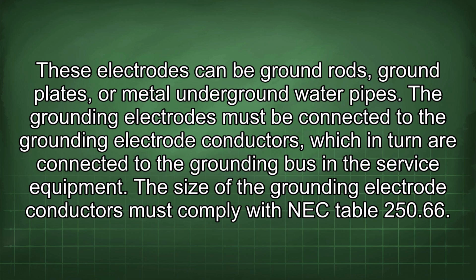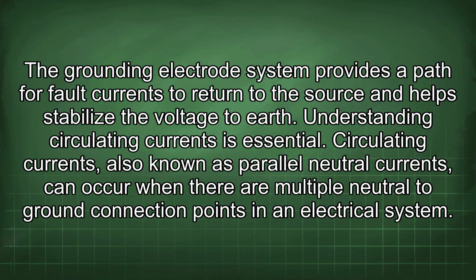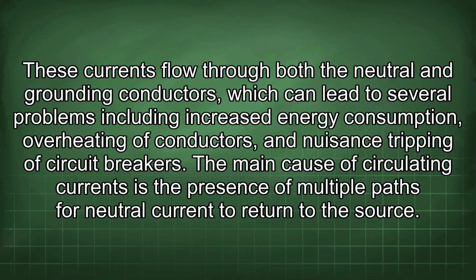in the service equipment. The size of the grounding electrode conductors must comply with NEC Table 250.66. The grounding electrode system provides a path for fault currents to return to the source and helps stabilize the voltage to earth. Understanding circulating currents is essential. Circulating currents, also known as parallel neutral currents, can occur when there are multiple neutral to ground connection points in an electrical system. These currents flow through both the neutral and grounding conductors, which can lead to several problems including increased energy consumption, overheating of conductors, and nuisance tripping of circuit breakers.